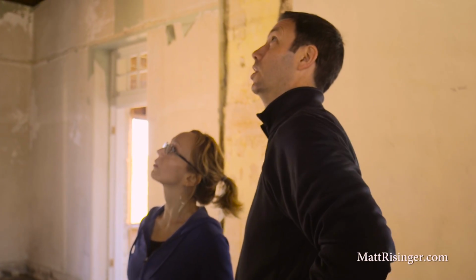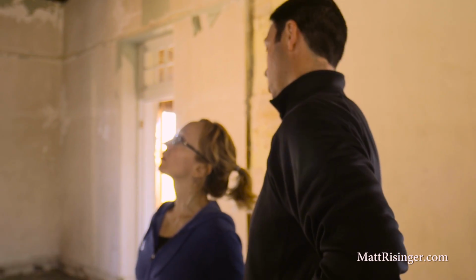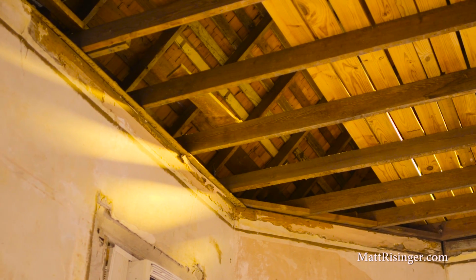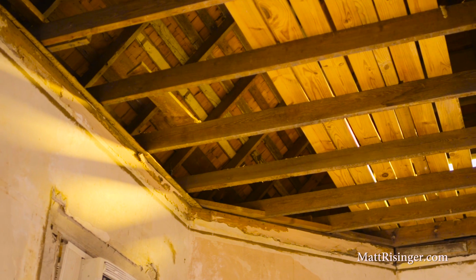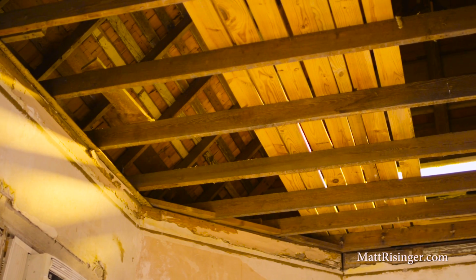So Kimberly, tell me first of all what the normal HVAC design looks like for most American houses. Well, it starts with usually 500 square feet per ton. That's how the equipment gets picked, right? And then let's fit the ducts wherever we can fit them. And so how is that different on our houses? You know, we're not doing just rule of thumbs. We're working with architects. We have very different houses, from this 1870s house with 2-foot thick masonry walls to another project with a ton of glass and really some striking contemporary architecture.